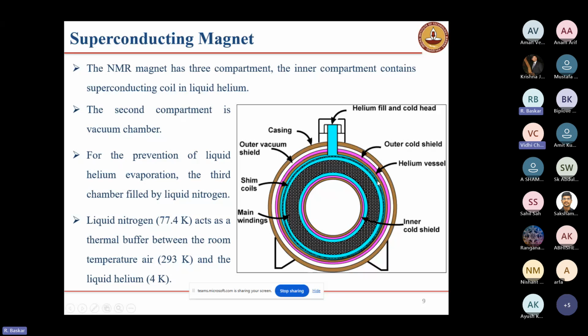I have one question here. Yes, sure, ma'am. Here at SAIF IIT Patna we have a JEOL make 500 megahertz NMR, and in this machine we fill helium twice a year. Up to what percent of the level are we safe? That depends on the magnet, ma'am. Engineers say maximum 30% is the safe level. When helium reaches 50%, we have to inform the engineers, because some transport delay and other things will be there. So up to 30% we can survive.